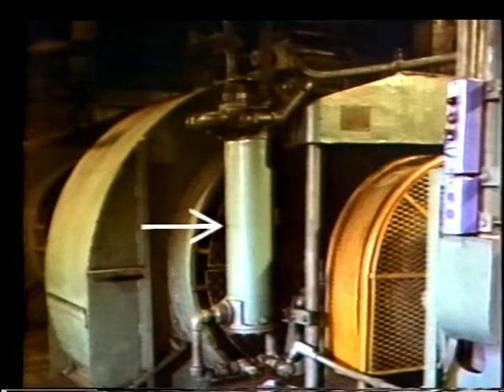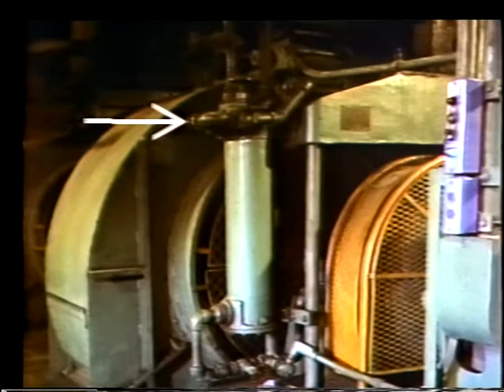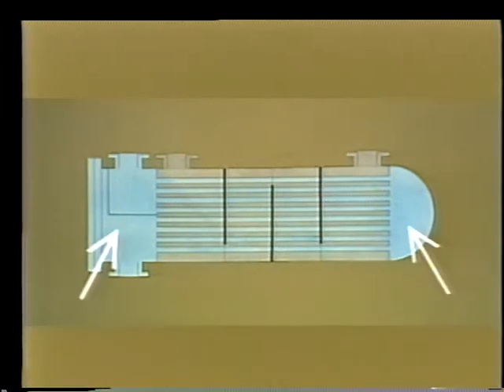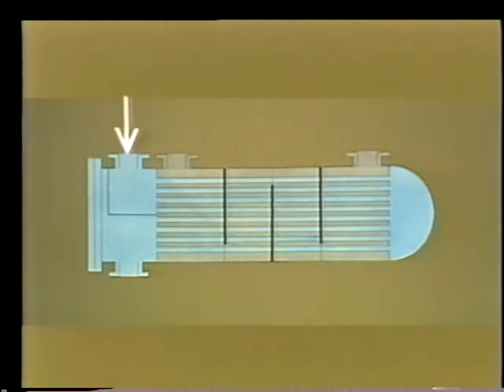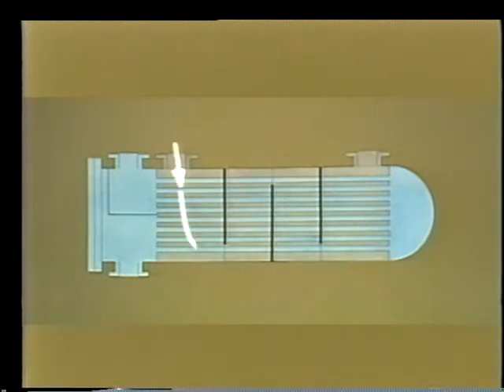This cooler does a similar job cooling the oil in a hydraulic coupling system on this motor driven fan assembly. Oil from the coupling system comes in here and is cooled by the flow of cold water before exiting to provide the hydraulic link between the motor and the fan. This is a very simplified cross section of a straight tube two-pass heat exchanger like these two coolers. The two chambers at the ends are the headers — in a condenser they're called water boxes. The cooling water flows in one side of the water box, goes through twice, and out the other side. The oil flows through the shell side in a single pass, and baffles in the shell cause the oil to flow over all the tubes several times.